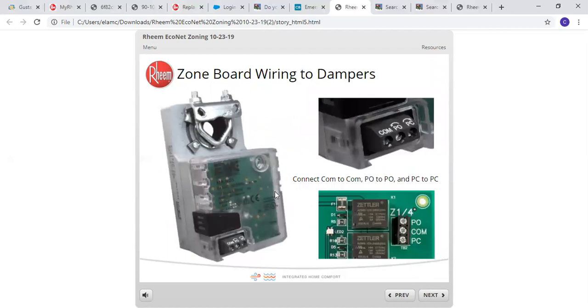And this is a close-up of the motor itself. As you can see, you've got your common, power open, power closed, and that's going to go to the corresponding zone, whether it's zone 1, 2, 3, 4, 5, or 6. You're going to make sure you're wired to the same thing here. If you miswire those, you will have a problem. If you miswire which zone it is, there again, the further you get along, you will end up with some error codes because it will recognize that. It won't tell you what the problem is necessarily, but it'll recognize you have an airflow issue.